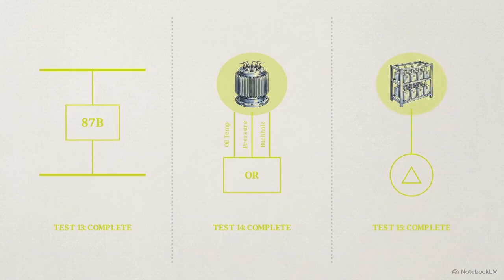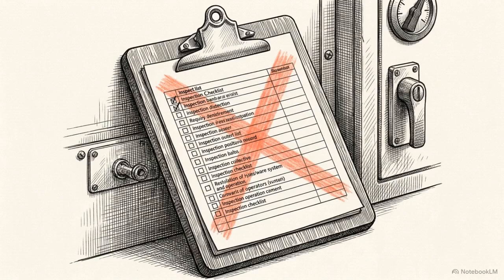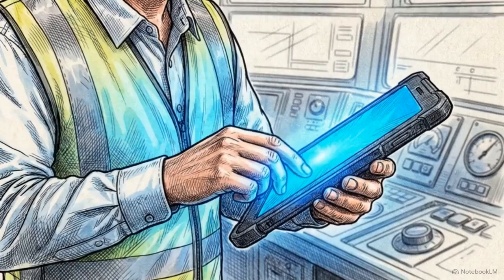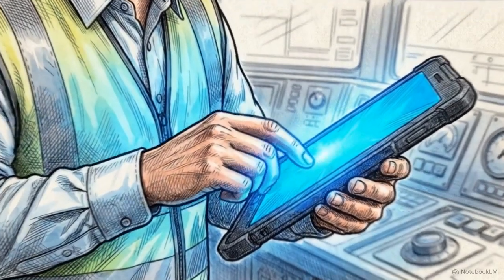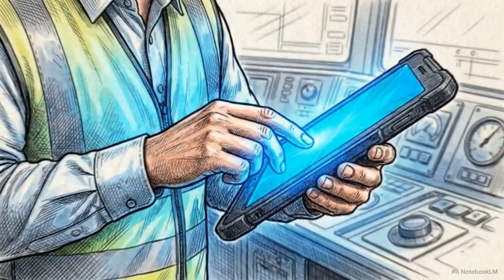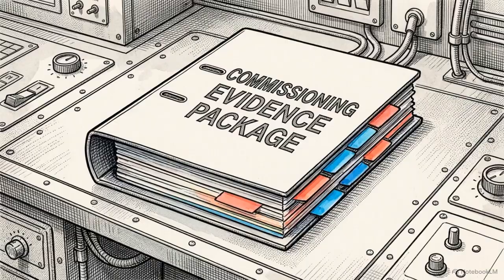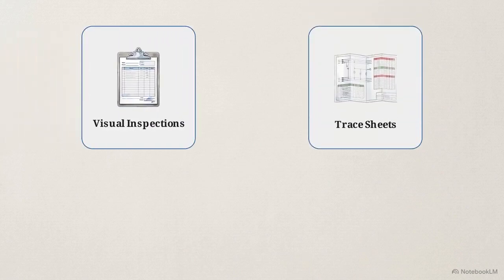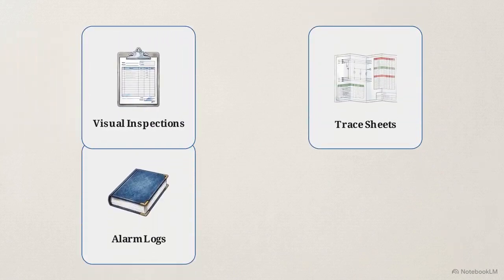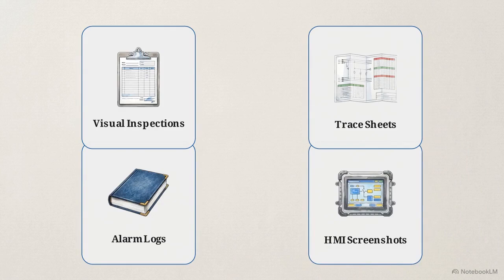During this tracing, the non-compliance rule is strictly enforced. Any missing ferrule, incorrect terminal reference, or drawing conflict is immediately logged as a punch item. It requires total correction and a complete retest. Once the physical and logical checks are complete, we assemble the final evidence package. This compiles signed visual inspections, point-to-point trace sheets, alarm logs, and screenshots from the human-machine interface.